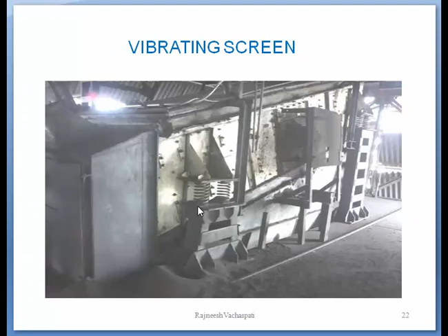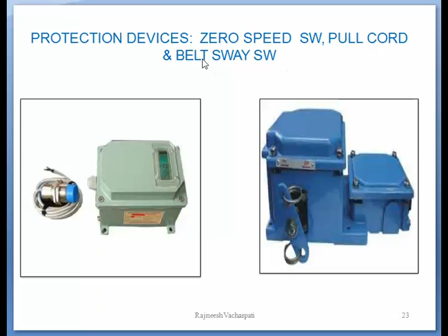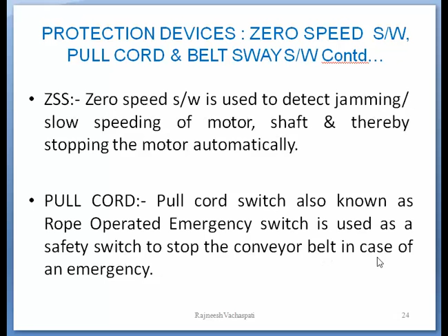There are various protection devices used in the coal handling plant, and mainly they are zero speed switch, pull cord, and belt sway switch. Zero speed switch is used to detect jamming or slow speeding of the motor shaft, and thereby it stops the motor automatically. When it senses any jamming or speed reduction of the motor, it automatically stops the motor. The pull cord switch, also known as rope operated emergency switch, is used as a safety switch to stop the conveyor belt in case of an emergency.